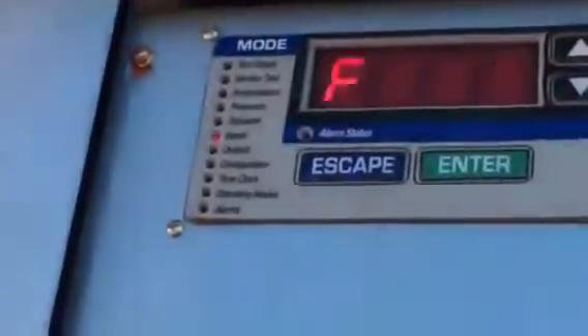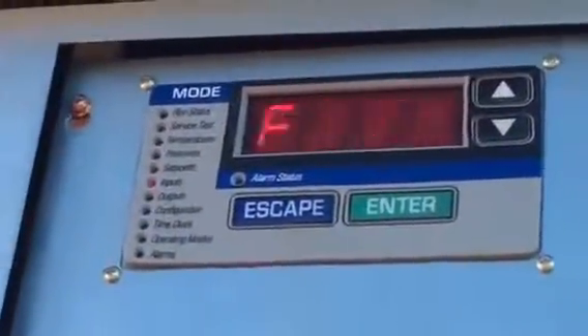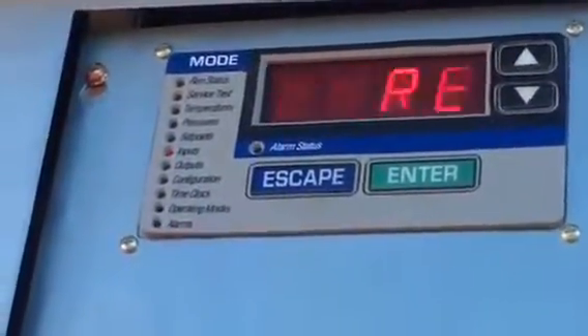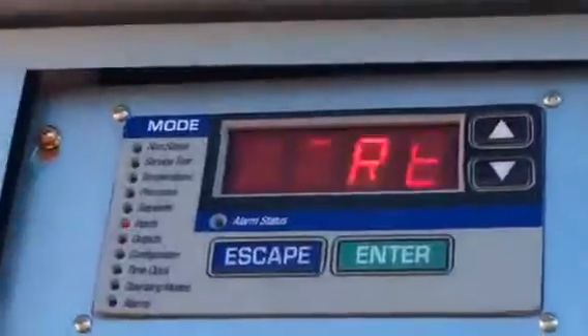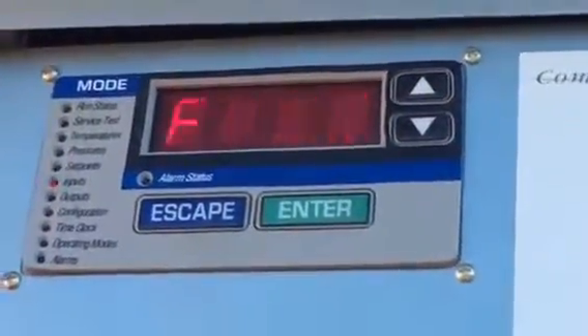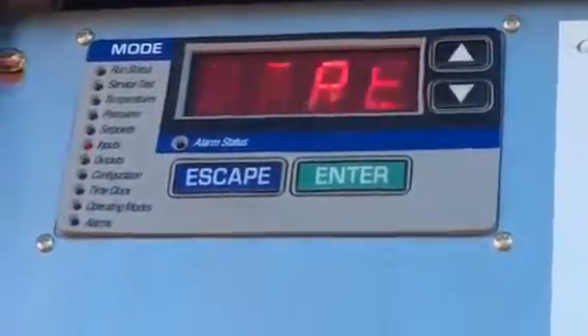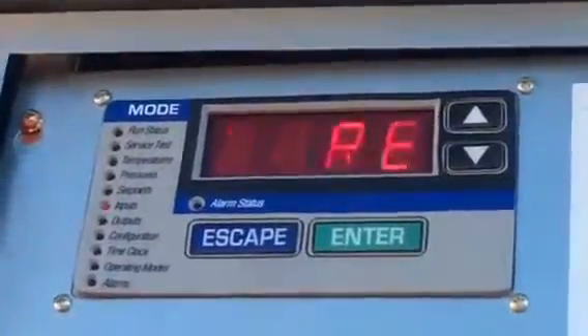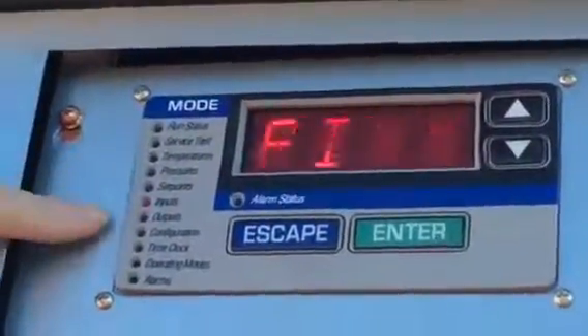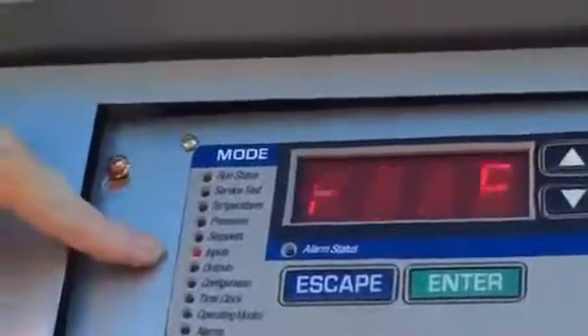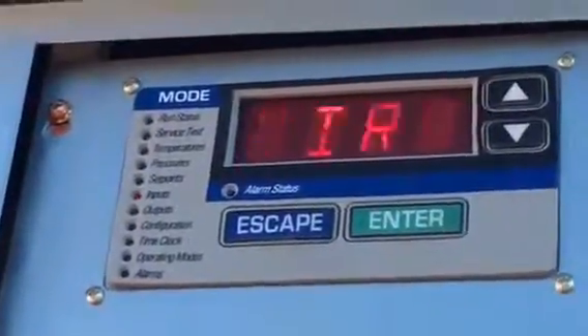On inputs, I can hit enter, general I, feedback, status, fire shutdown. Like if these had been set up for fire shutdown and I have a unit that's sitting there not running, I can always go in, status, one of the HVAC modes is going to be fire shutdown. So right off on my view that scrolls by always, it'll tell me why it was shut down, fire status. The fire damper shut, causing the unit not to run. Or I can always go down here to inputs and see that I had that fire shutdown command.